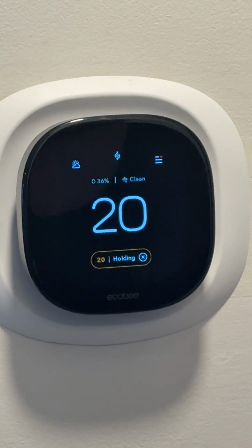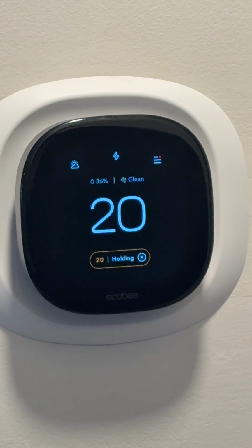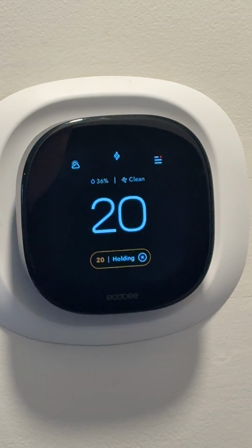We're just doing a quick tutorial video on how to set up an Ecobee thermostat for Winnipeg, Manitoba. The reason we set up our thermostats differently than the rest of the world is we have very low electrical rates and very low natural gas rates. So our economic set point or balance point is about -8. We can run our heat pumps to -8 and it'd be the same cost as using a high efficient natural gas furnace. Your goals as a customer might be different.